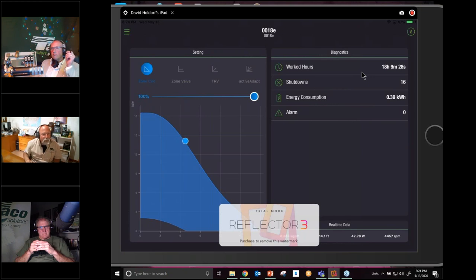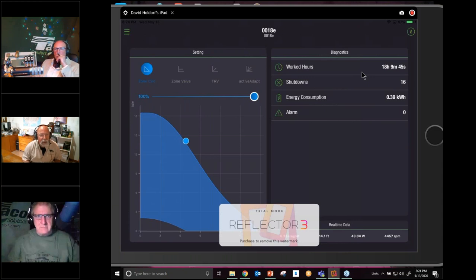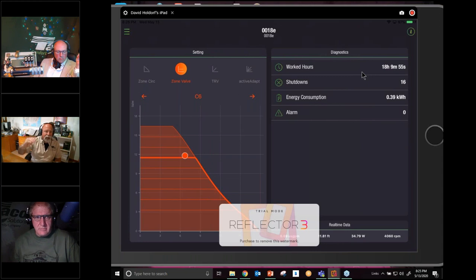This particular test unit that Dave has behind him has about, what would you say that is, about 13 or 14 foot of head, right? Yep. Well, 14, that's where everything opened. That's with everything calling, and you're normally not going to need that. So, Dave, if you would touch the zone valve button, what I would recommend you do is go down one step. So touch that next lower button, lower, the other lower. Okay, bring it one more where it was. Well, no, it was just under 12. Now take it down one more. Maybe that's what it was where you had set it.